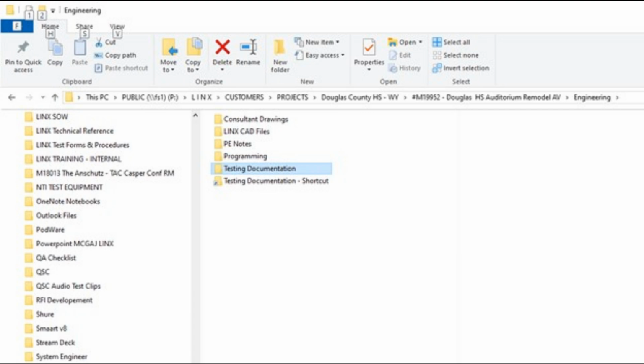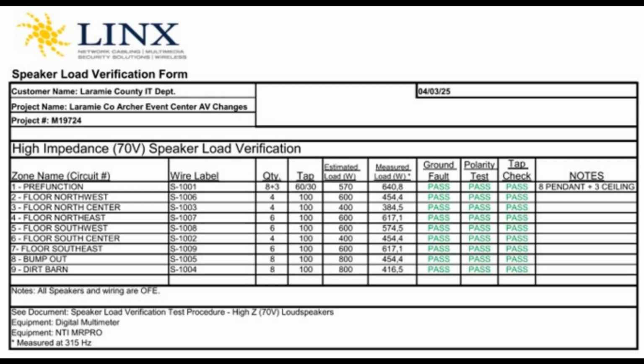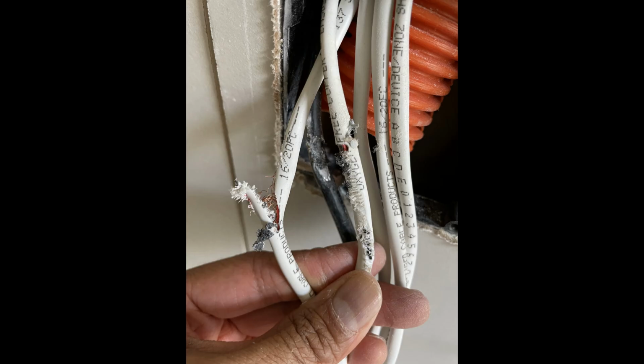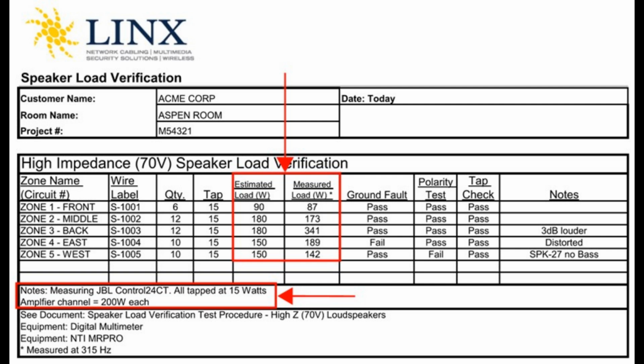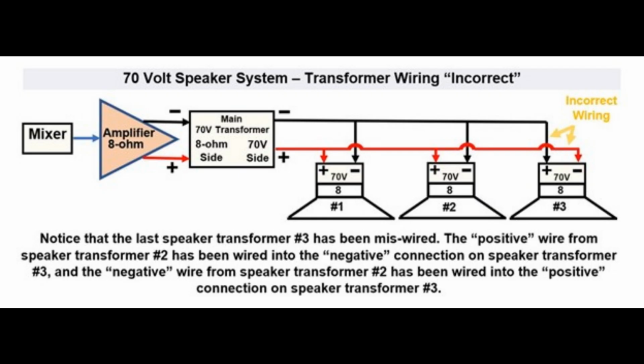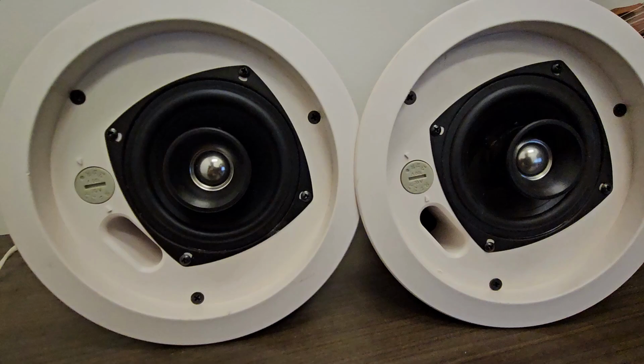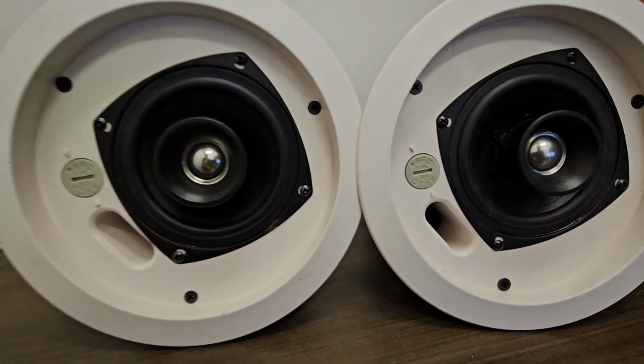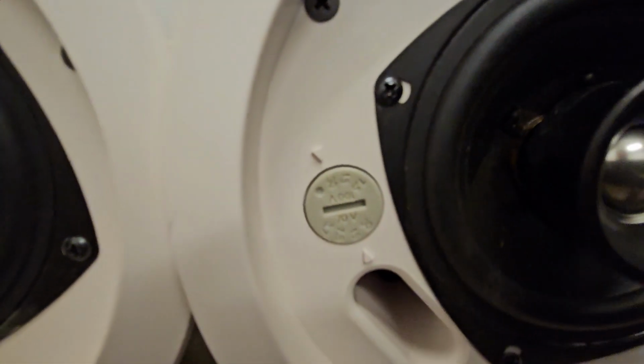test documentation folder. This new LINX standard for verifying 70-volt distributed speakers will provide the service and engineering team with the following information. The field speaker wire has no physical damage such as frayed sheath or shorted conductors. The speaker circuit overall load impedance, measured in watts, falls within the expected range and does not exceed the amplifier's power capacity. Speakers are wired with correct polarity. Speakers are tapped at the same value, resulting with even speaker coverage and sound pressure level.